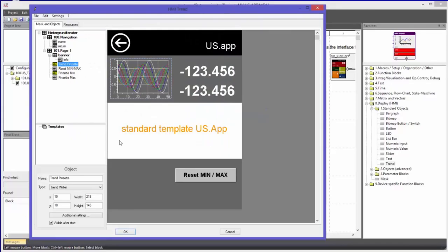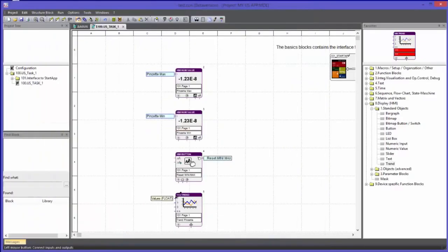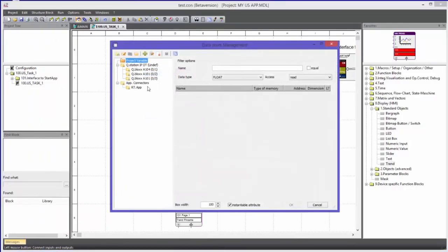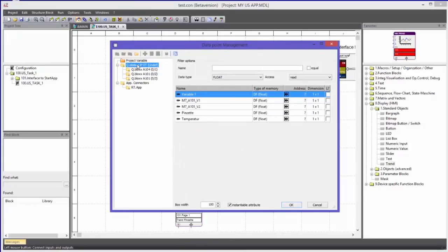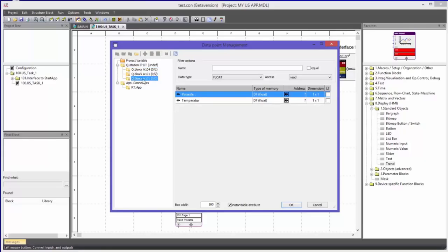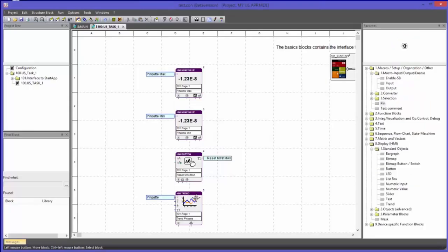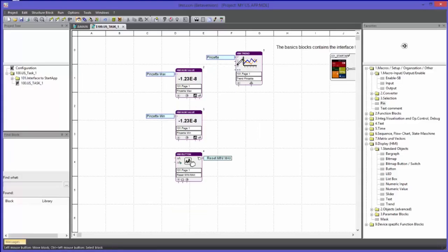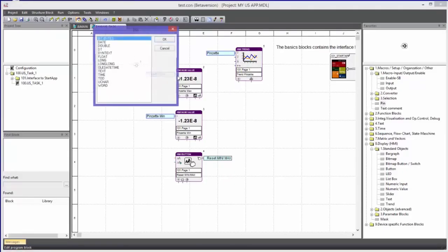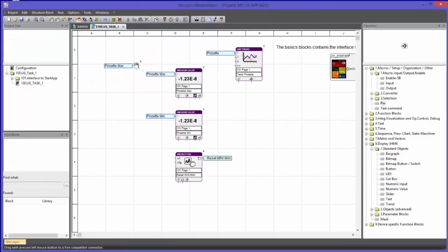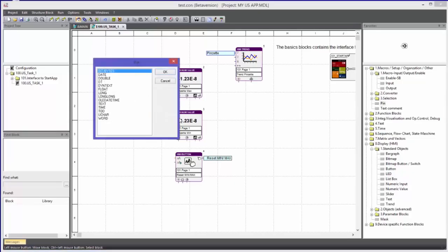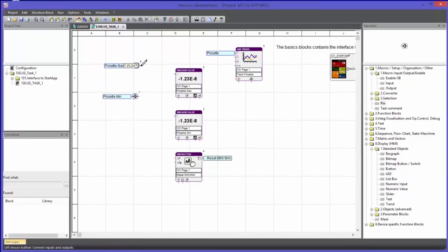Now this is my current configuration. I will confirm that with OK and assign this trend block to the IO variable tweezers over the section QStation IP DT — not over the application connectors — so I can access the IOs directly. Here in the third Q.bloxx module A101 I can find the tweezers. To scale the trend in the Y axis direction automatically, I will link the min/max values of the scales using a Pin block to access the data of the block attribute. I will implement another Pin block and connect the results with the corresponding values.